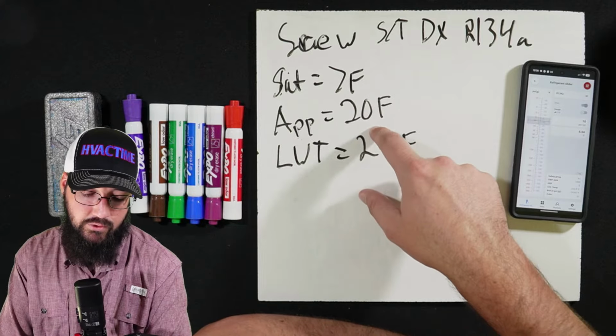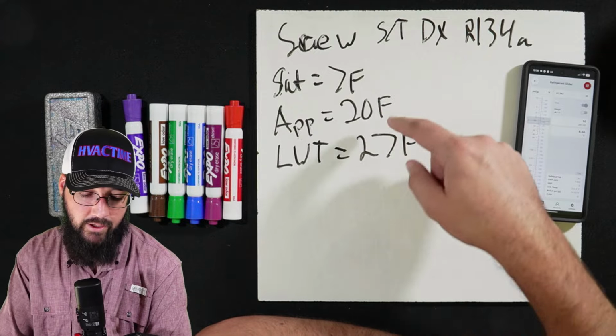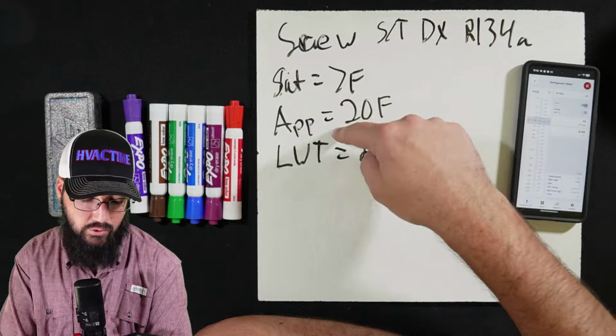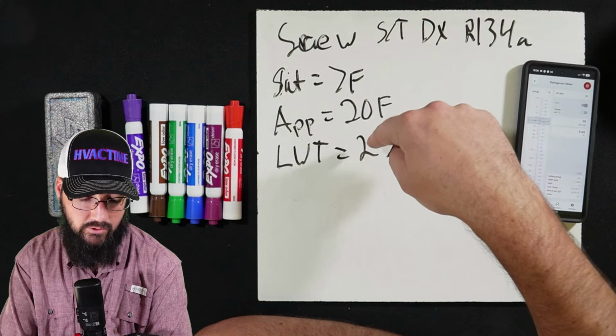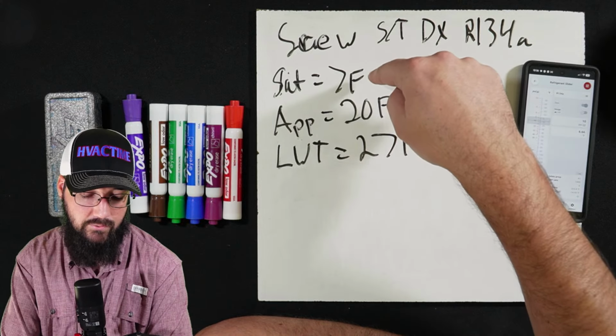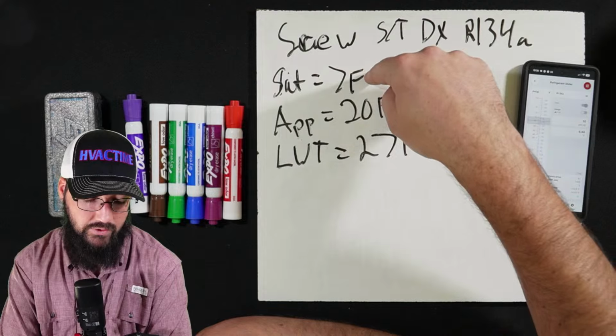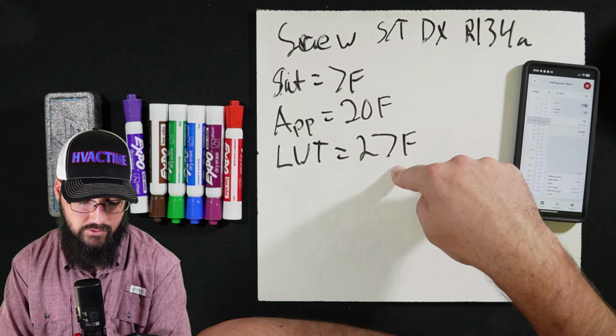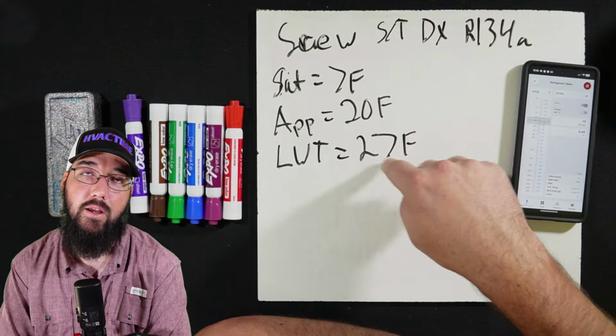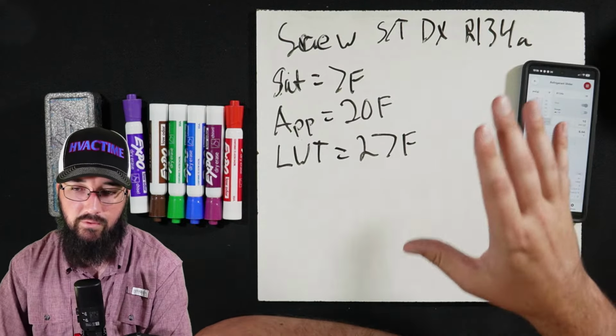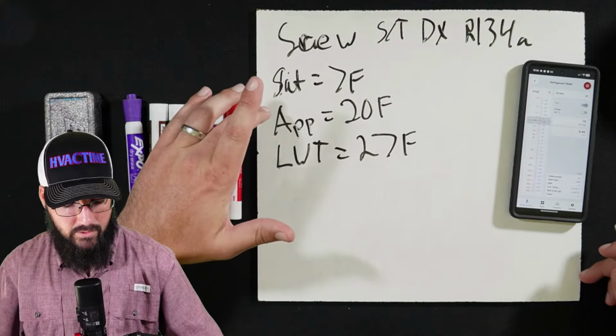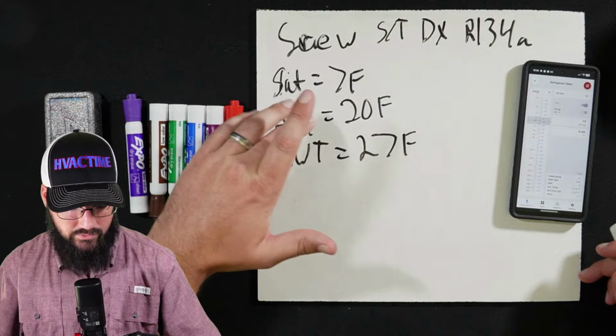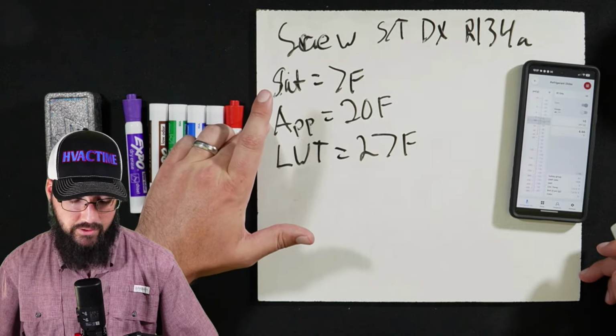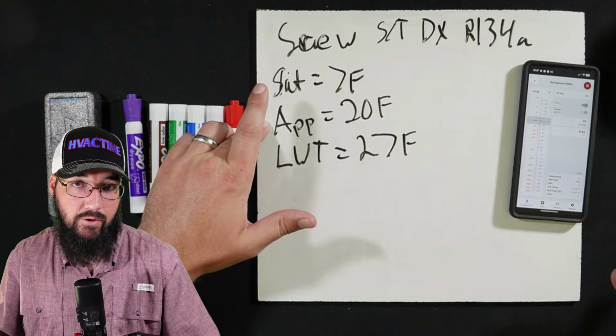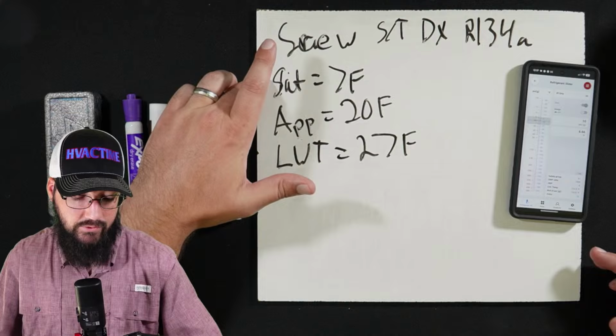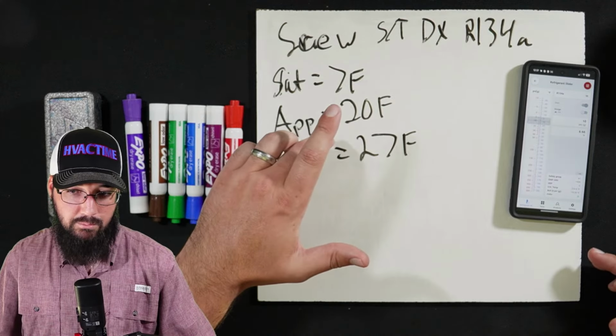Our approach, you said, is 20, which would mean that if we're running the math right, to get the approach, we have to subtract our saturation from our leaving water. Hang on, I'm screwing myself up. Yeah, leaving water minus saturation gives us our evaporator approach. Getting twisted up here. The difference between those is 20. That's how we should be getting approach. So one thing is, how are you calculating the approach? Are you subtracting saturation from leaving water, the difference being 20?